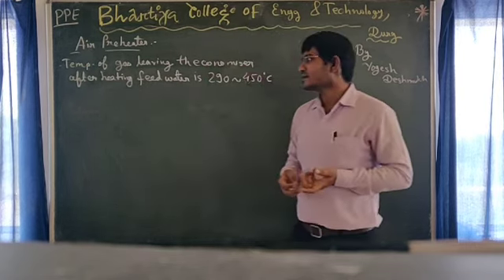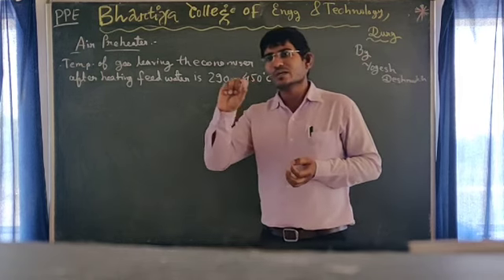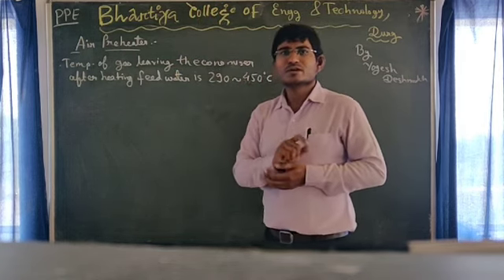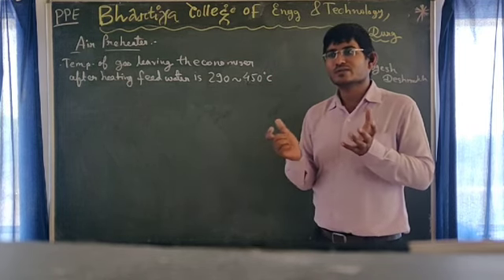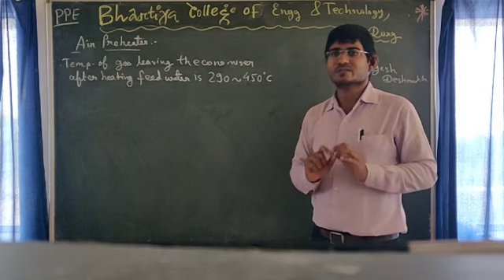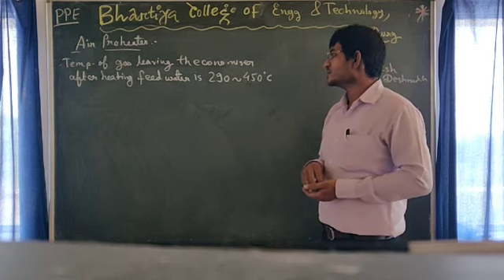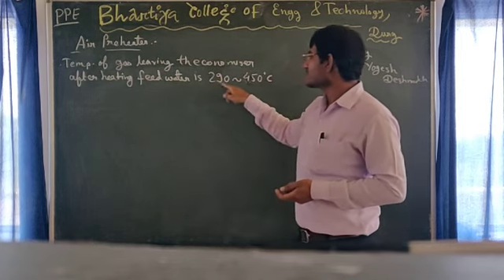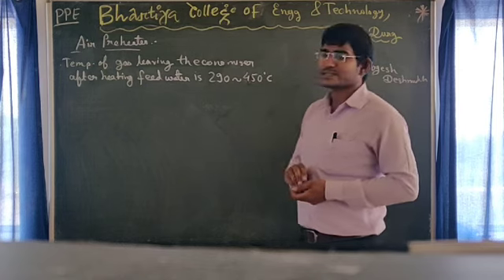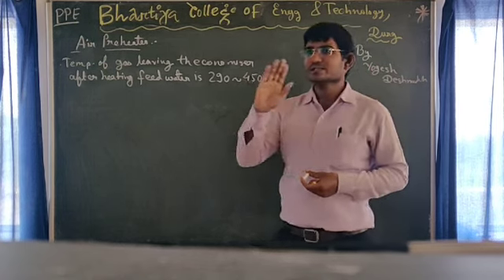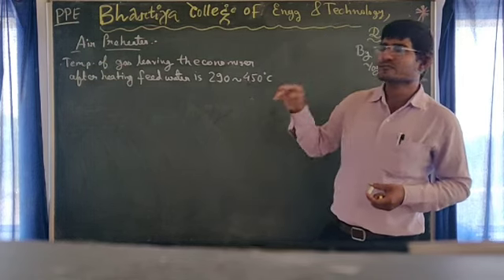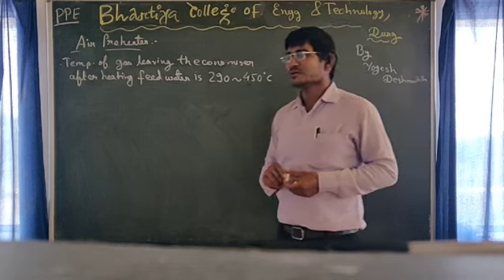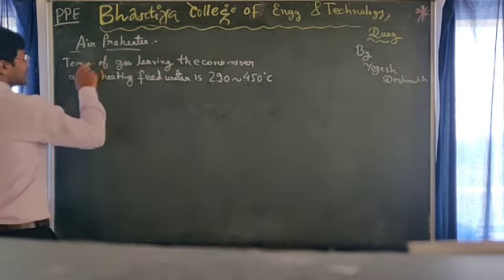Why we are using the air pre-heater? In a boiler, when the flue gas flows through the re-heater, superheater, and after it completely passes through the economizer — where the feed water is heated to a certain temperature before entering the boiler — the flue gas temperature after leaving the economizer is 290 to 450 degrees centigrade, which is too high. If we pass this flue gas through the chimney to the atmosphere, it will be wasted. So we have to utilize this flue gas temperature, and we install an air pre-heater after the economizer.